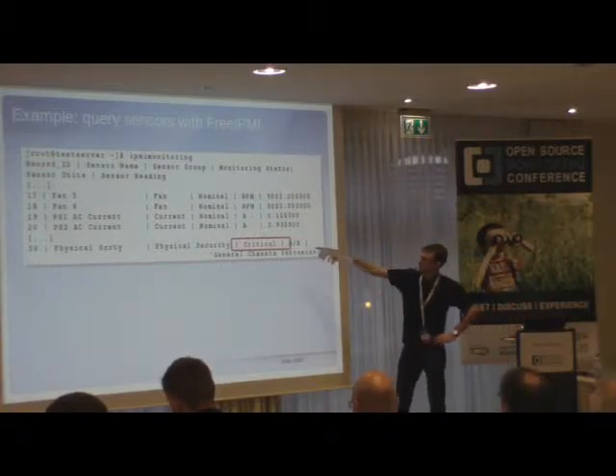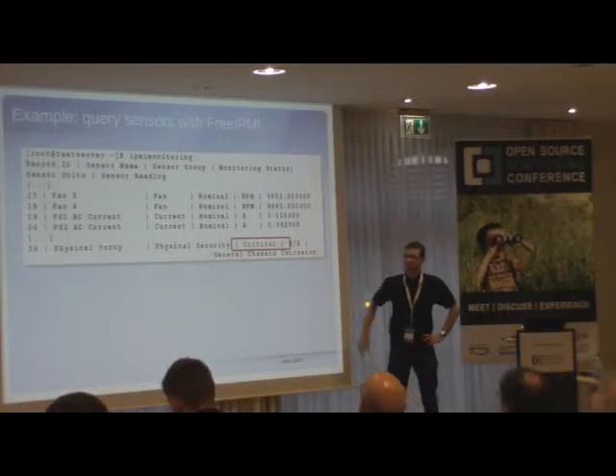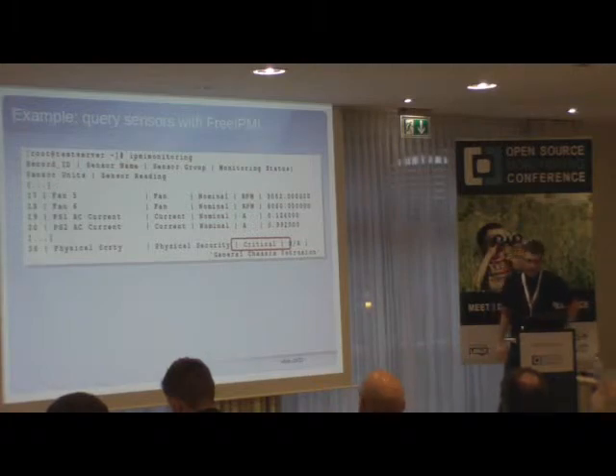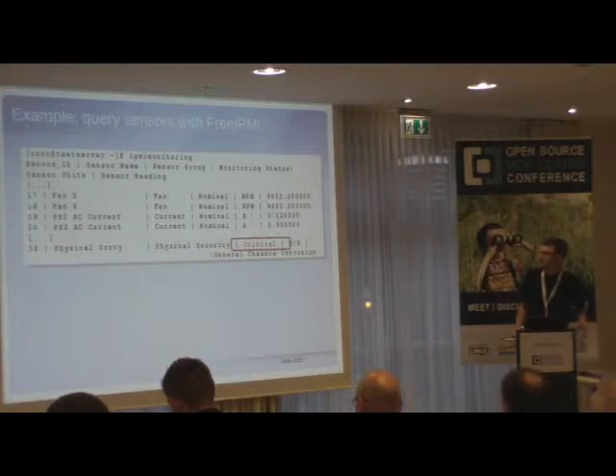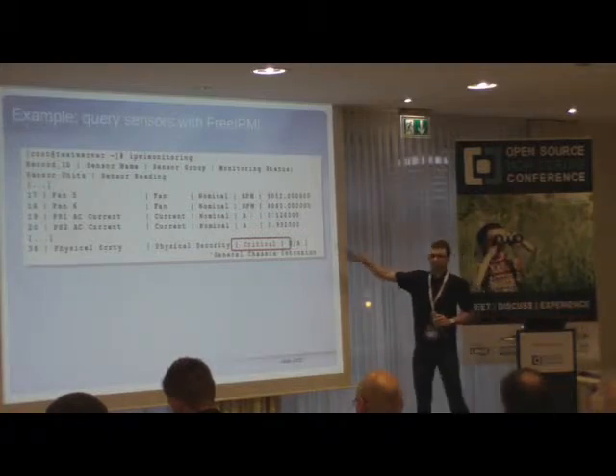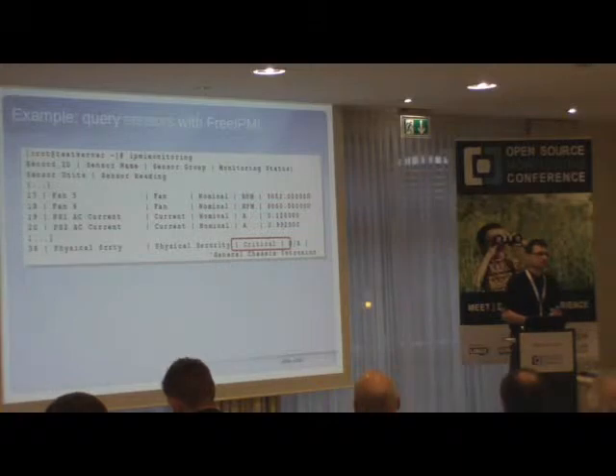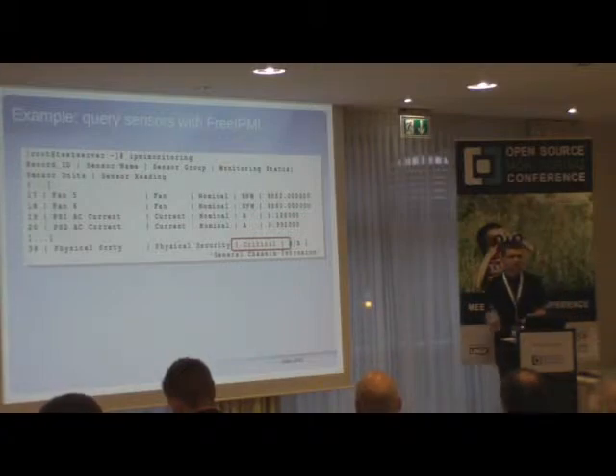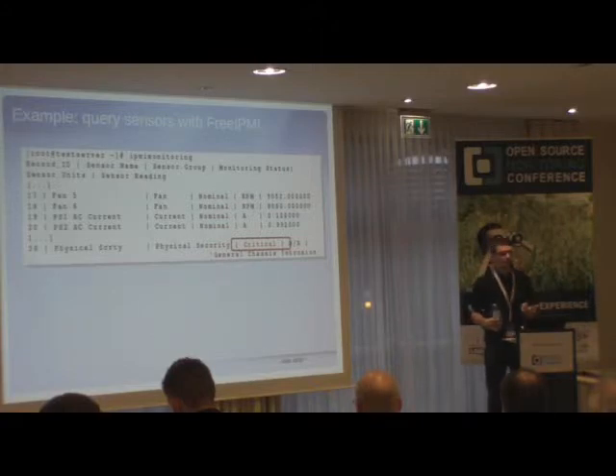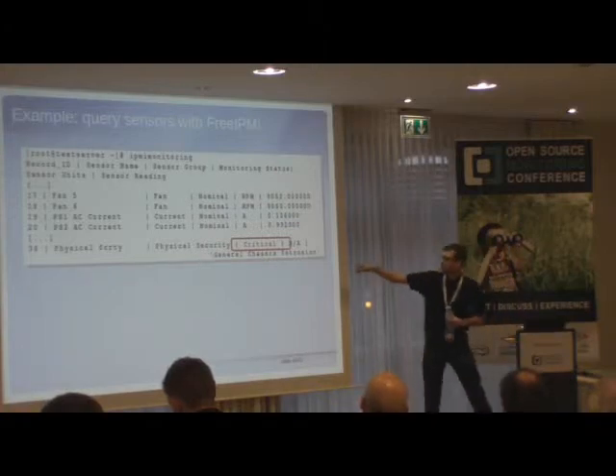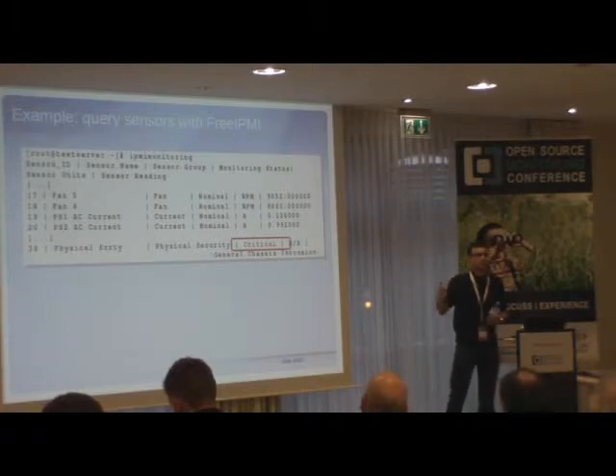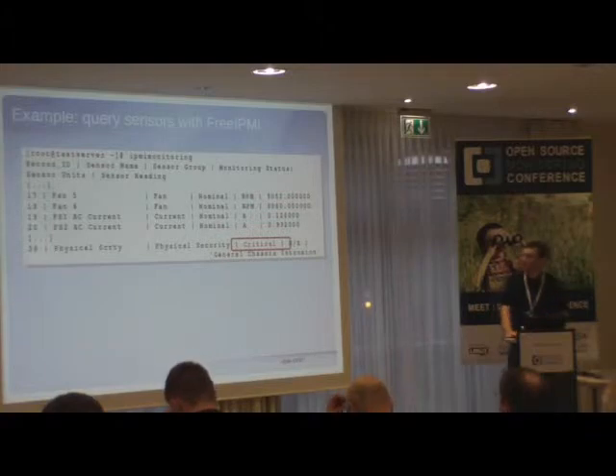Here we see a physical security sensor with the state 'critical' because chassis intrusion has been detected. For those discrete sensors, one might think the yes/no information could mean different things to different people. For example, when you have redundant power supplies and a server with three power supplies, where just one is enough to run the server — do you want a warning when only two are running? This can be configured within the free IPMI configuration.